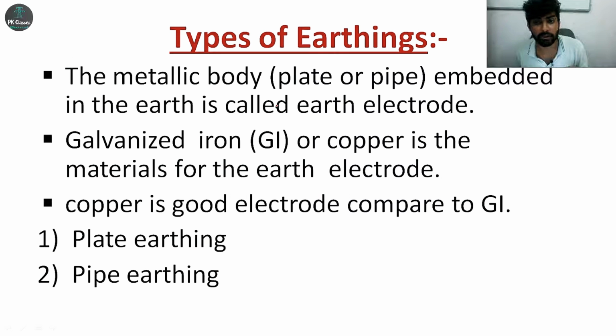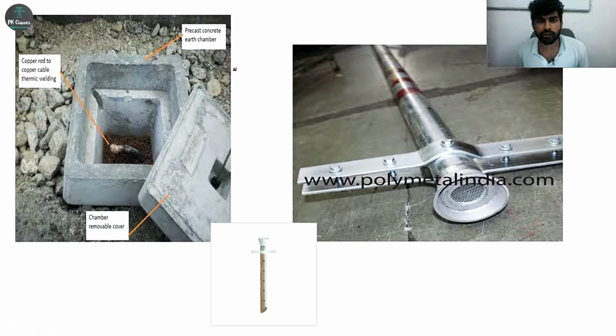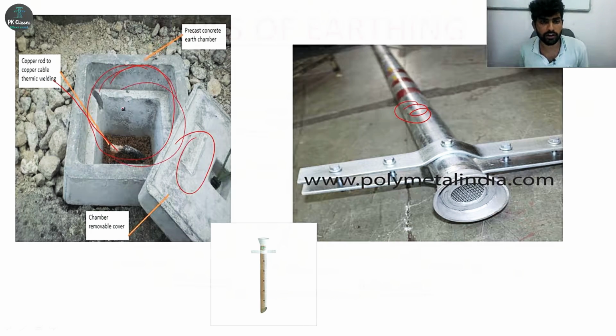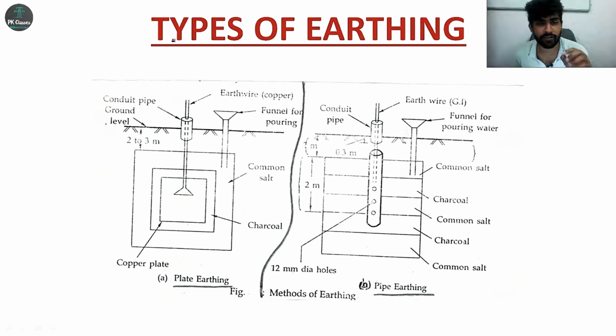Next, types of earthing. Based on the earth electrode we insert into the earth, one is plate earthing, another is pipe earthing. These two are made of galvanized iron or copper. I have taken some photos for understanding. There is an earth electrode, which we insert into the earth pit, and this is the earth wire, and this is the earth chamber for maintenance purposes, and this is a cover for closing the earth chamber. We'll discuss types of earthing in detail.